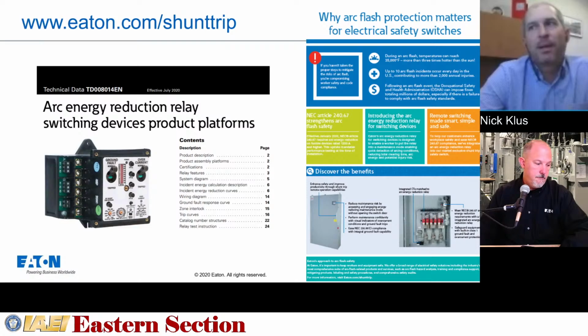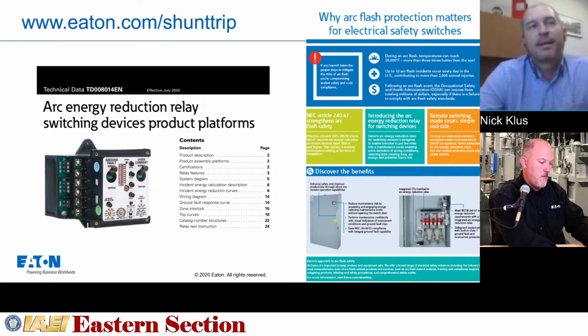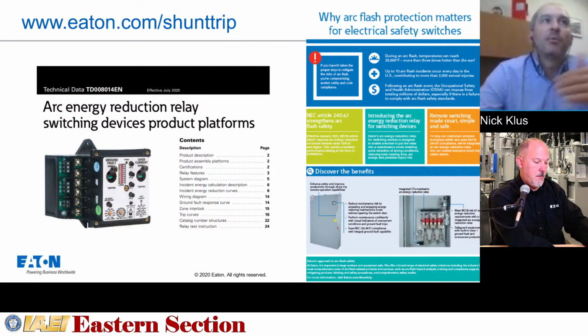But again, the UL standard does say that there are instances where somebody would need to do this. So you need to provide a provision to defeat that interlock and be able to get into that switch with it in the on position. So yeah, you can technically do that.